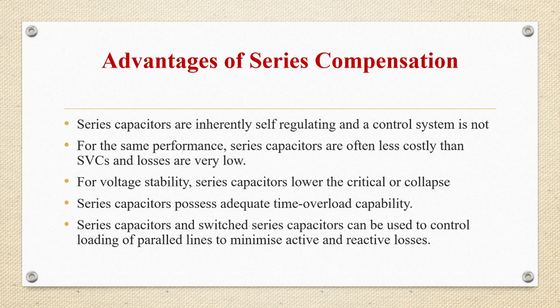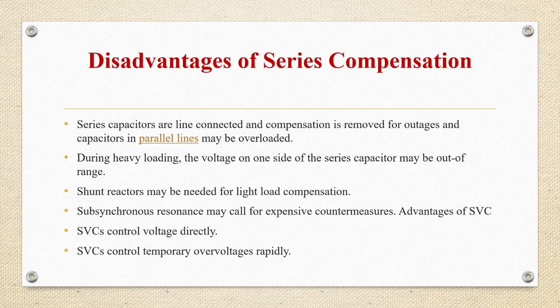Series capacitors are line connected and compensation is removed for outages, and capacitors in parallel lines may be overloaded. During heavy loading, voltage on one side of the series capacitor may be out of range, and shunt reactors may be needed for light load compensation. Subsynchronous resonance may call for expensive countermeasures. Advantages of SVC: SVCs will control voltage directly and control temporary overvoltage rapidly. Disadvantages of SVC: SVCs have limited overload capability and they are very expensive.